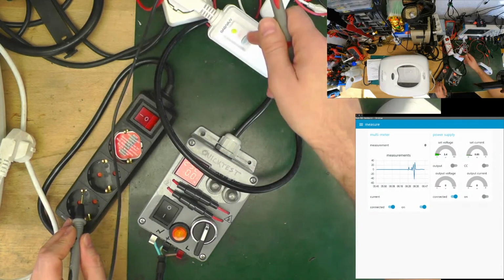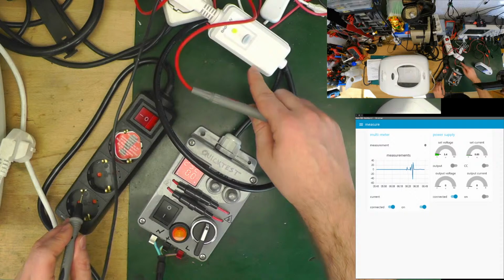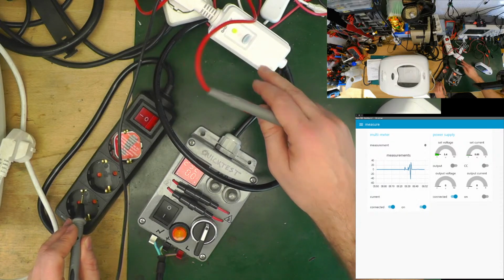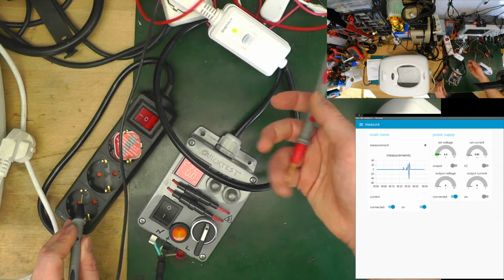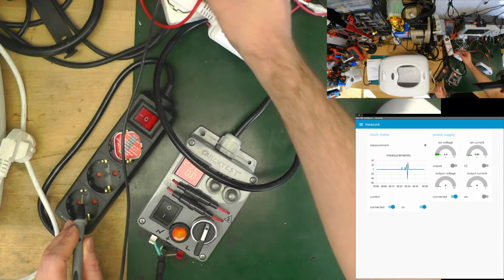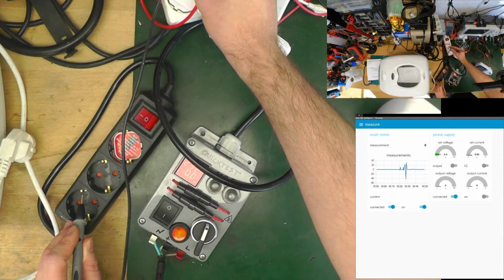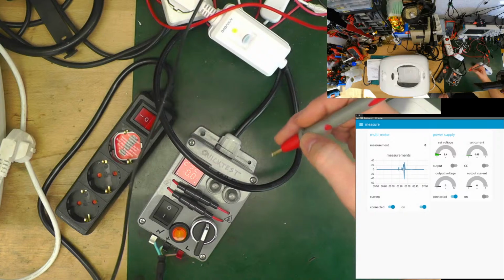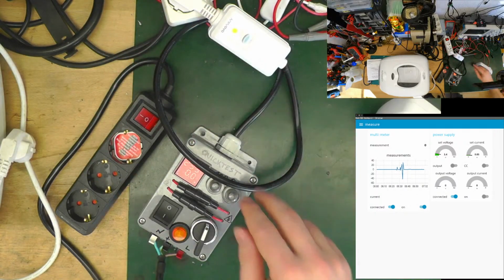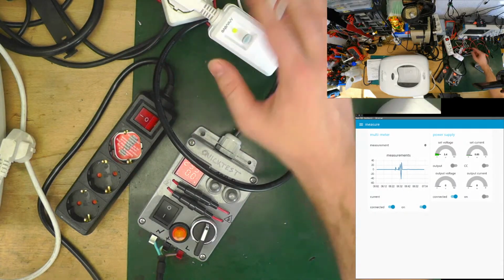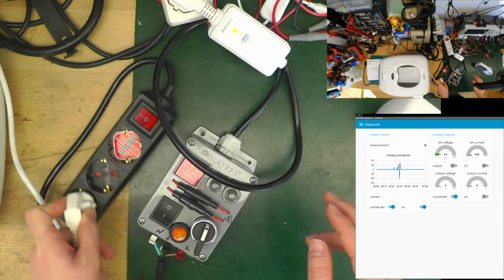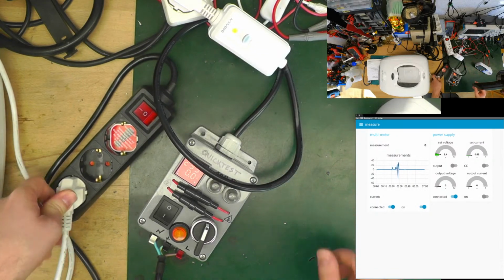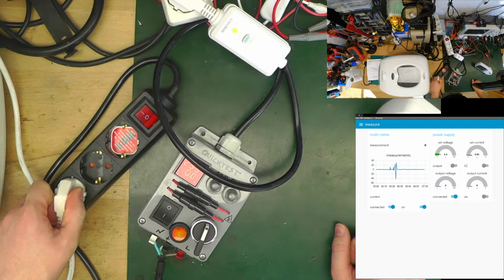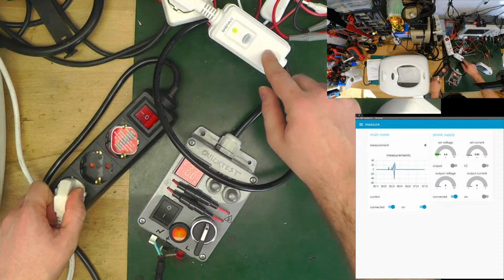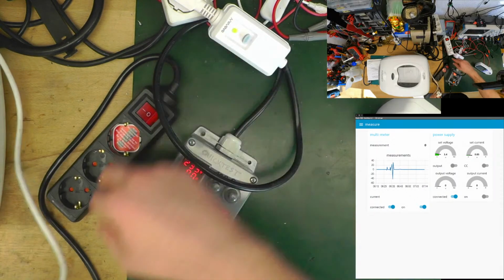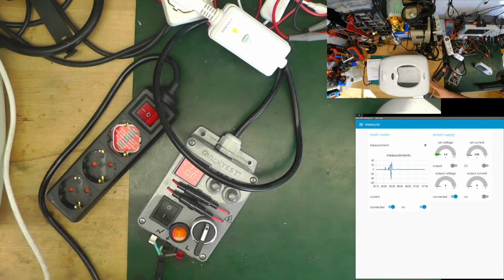But the RCD doesn't actually need earth. It just measures the difference between live and neutral, and if the difference is more than 10 milliamps, it should trip. So even if I don't have earth, I should be fine. This thing should still work. But there is earth, meaning that no matter what happens, at least it works. Yeah, it should also work with earth, because even if the earth is not connected here, if you touch it, you are becoming earth.